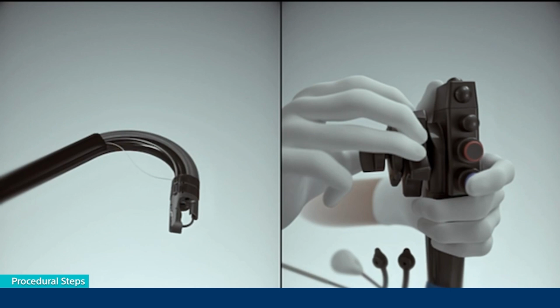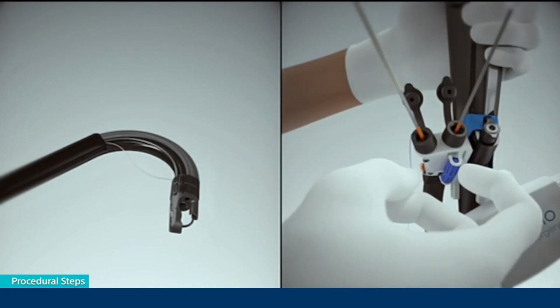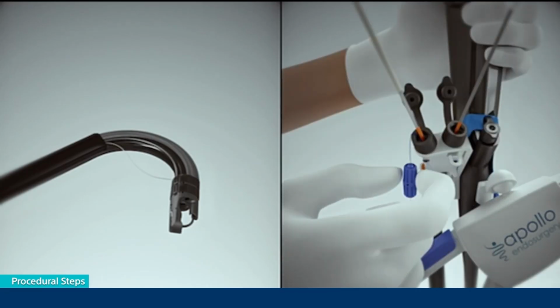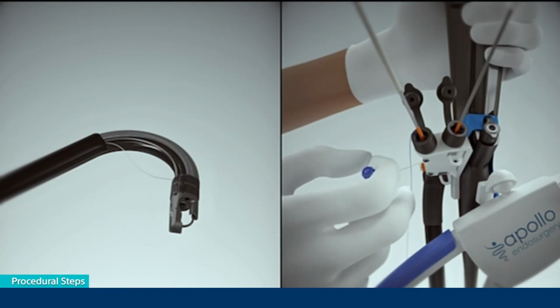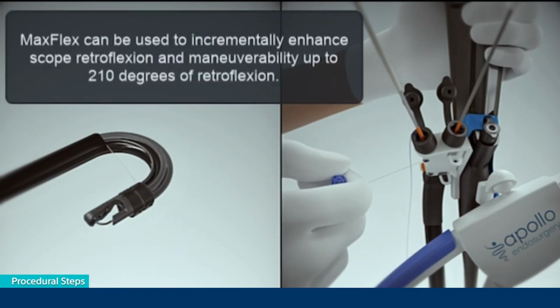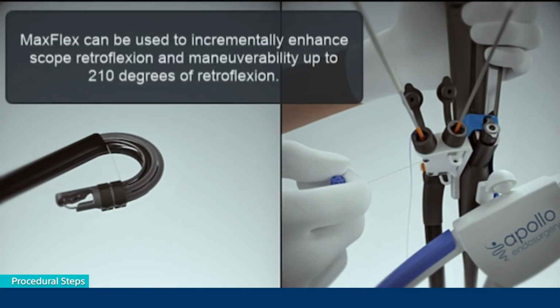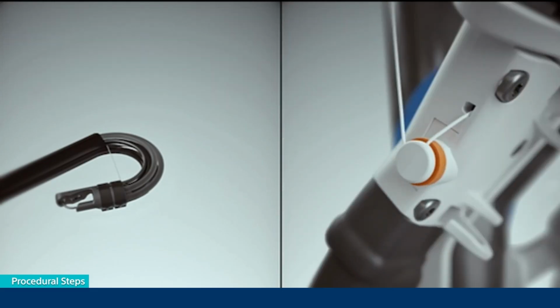Step 2. Keep the suture in your primary channel out of the way by holding it in your scope hand. Step 3. Disengage the blue MaxFlex pull string pill from the underside of the device handle. Step 4. Pull string straight out from device to increase articulation to desired position. Step 5. Wrap pull string around orange brake washer on side of device a minimum of 2 times to secure device position.